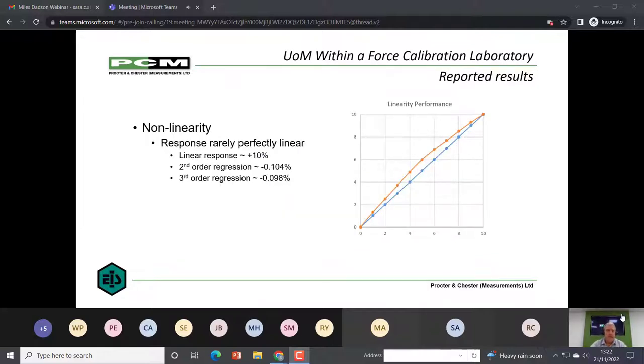evaluations now. So for non-linearity, I've never seen a device that will give you a perfectly linear response. You can get very close, but it's never perfectly linear. This is a vastly exaggerated response, where the straight line response is denoted by the blue line, and the actual response of the device under test is the orange. I'd be very suspect of a device that performed like this in real life.